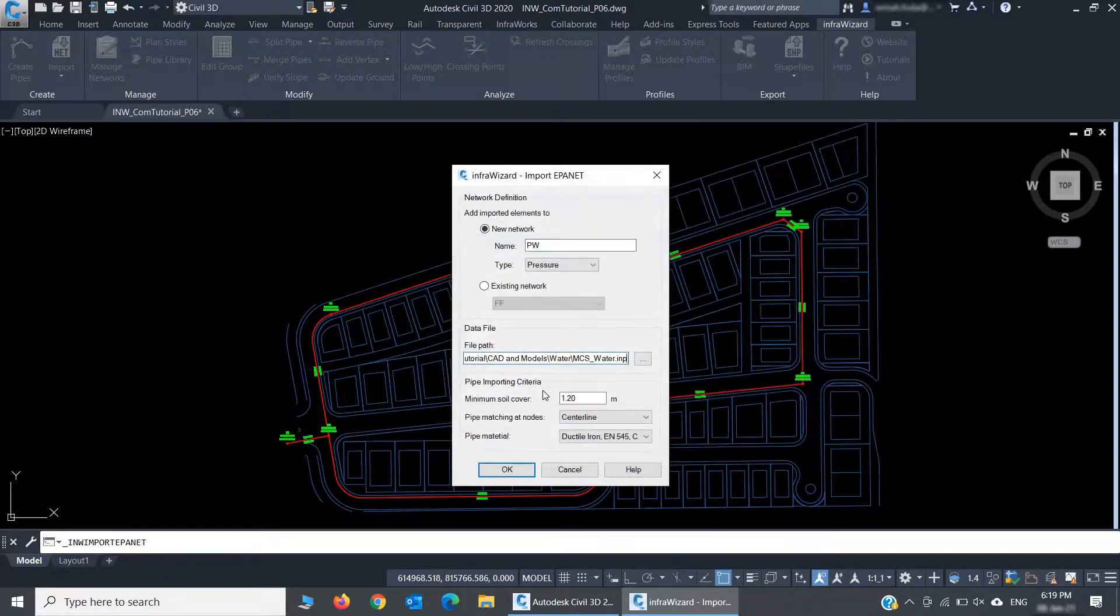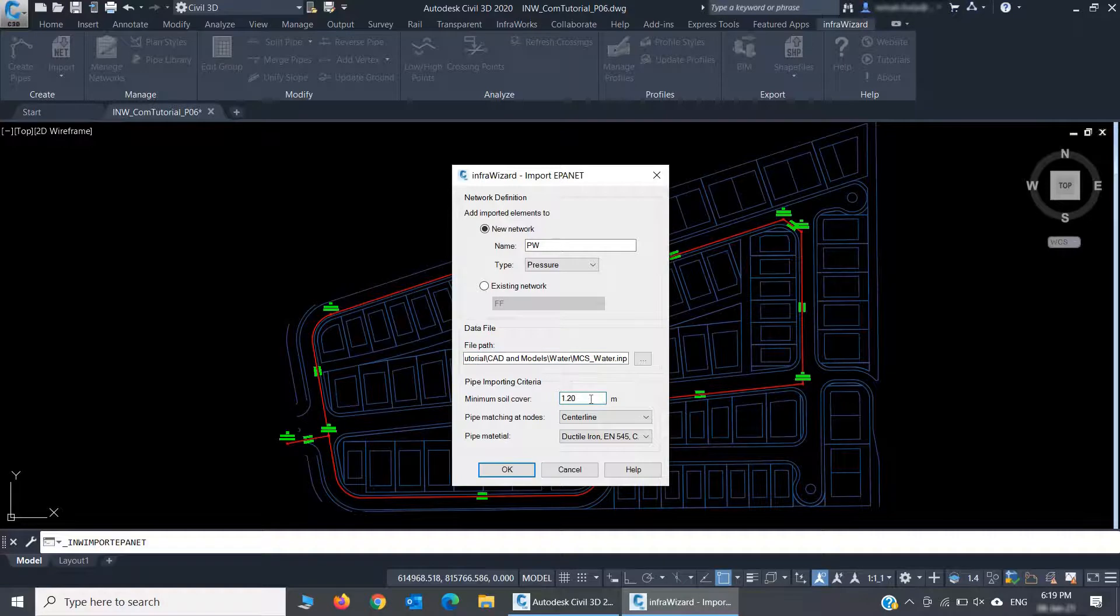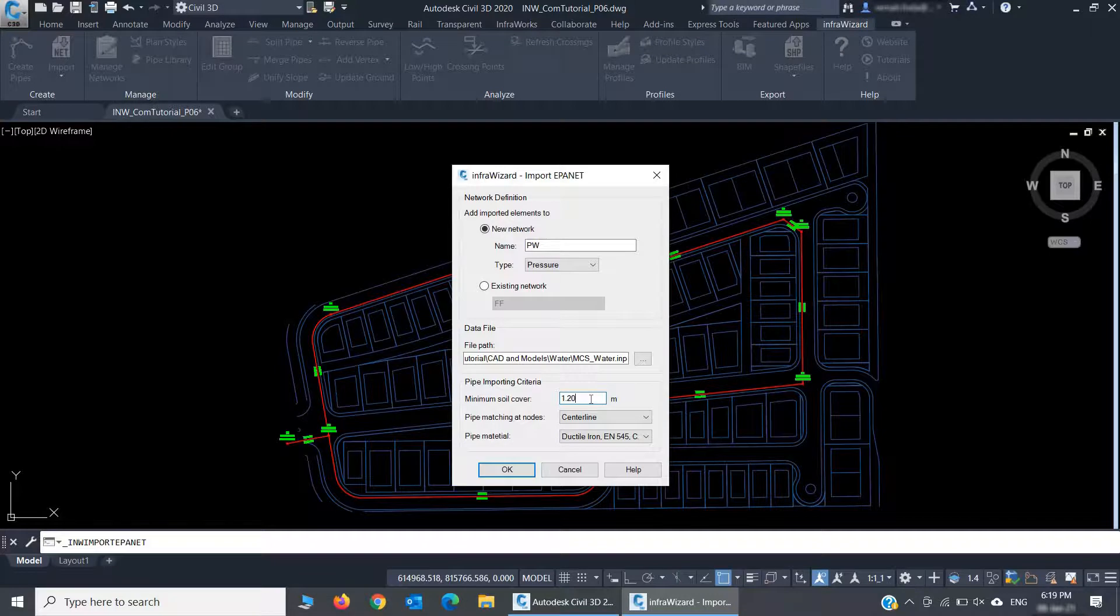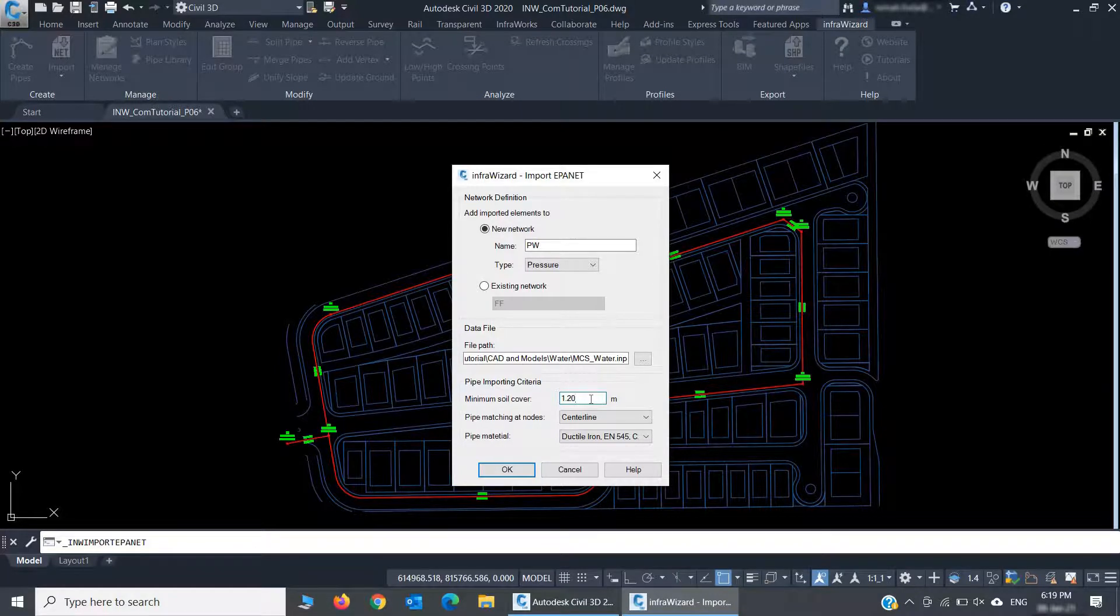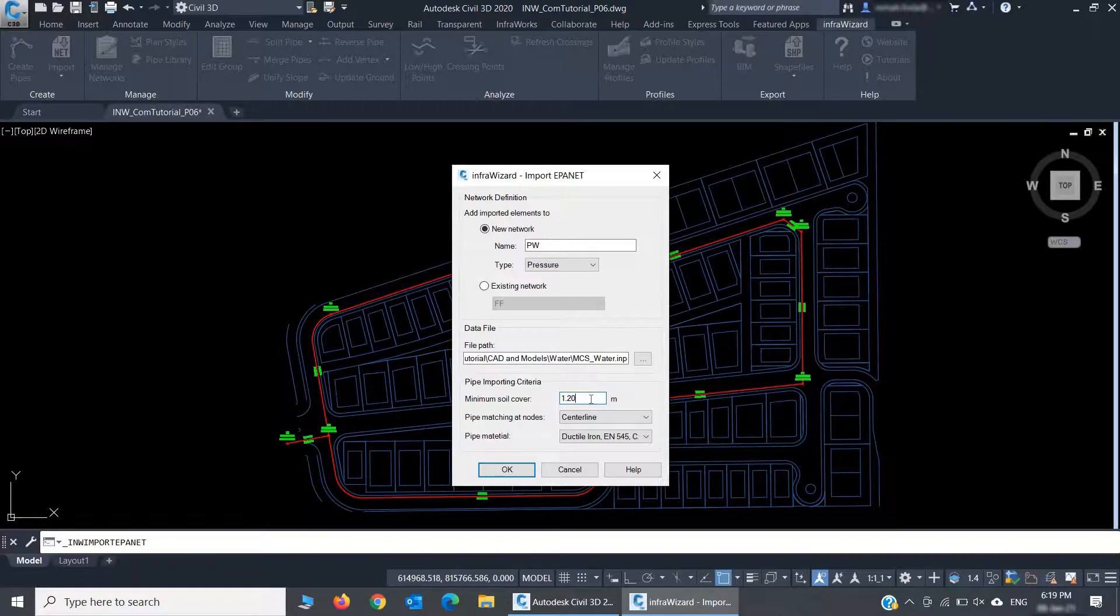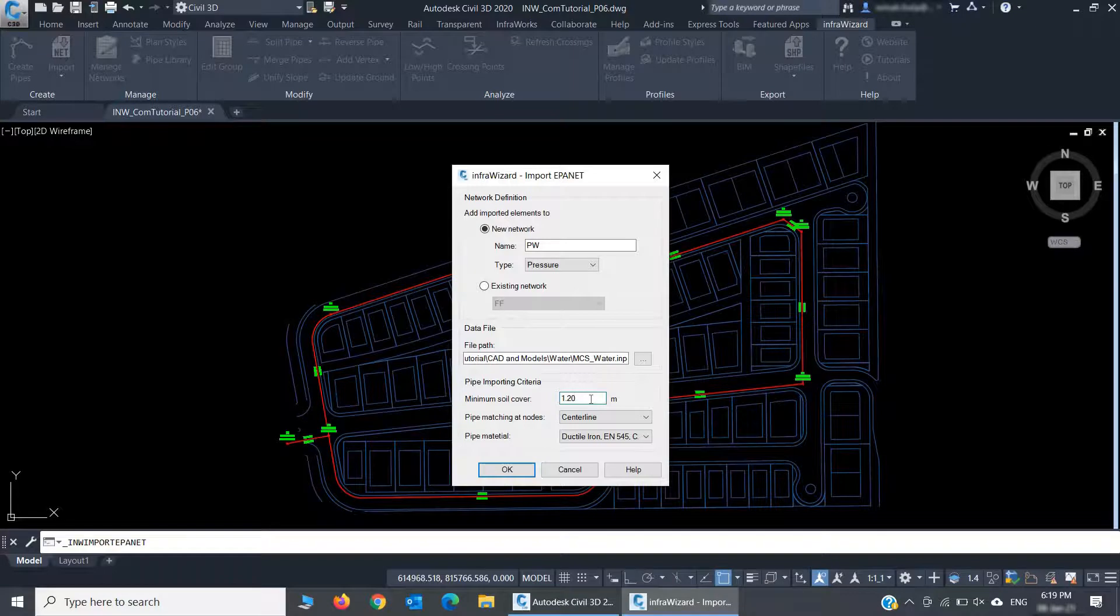Here I should set some criteria that InfraWizard uses during the import process. The first setting is the minimum soil cover. InfraWizard needs this because an EPANET model contains only one elevation value at each junction. InfraWizard assumes that this value represents the ground level at the junction, which is the common practice. It then uses the minimum soil cover to offset the invert levels of the pipes from these ground levels.